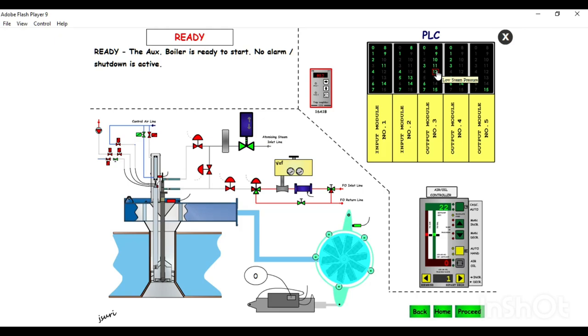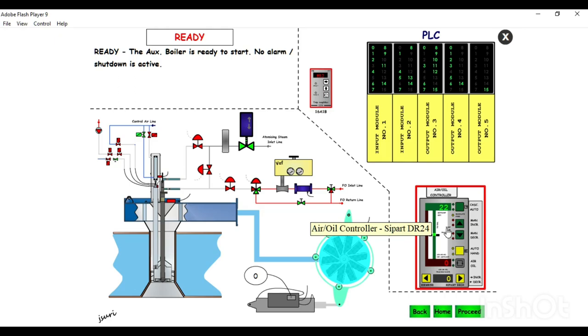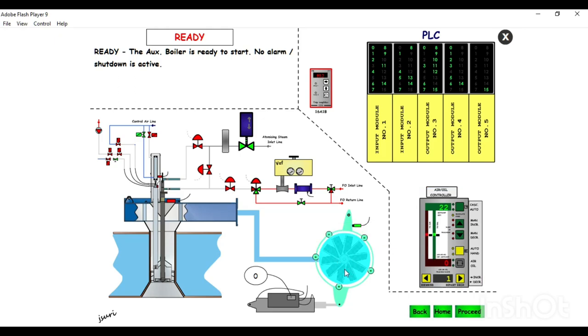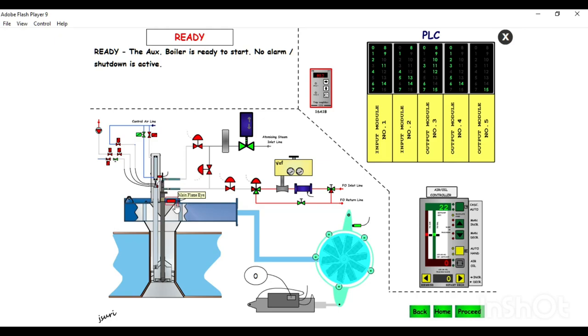The PLC processes all these outputs and we can see on the boiler main screen which alarm it is giving. This is the trip amplifier used for starting and stopping of the boiler. Here we have the air and oil controller located on the boiler, the boiler FD fan, fuel oil recirculation valve, atomizing steam controller valve, control airline, and the igniter inserted feedback switch which senses whether the igniter has been inserted. We also have the main flame eye which senses whether the main flame has been established.